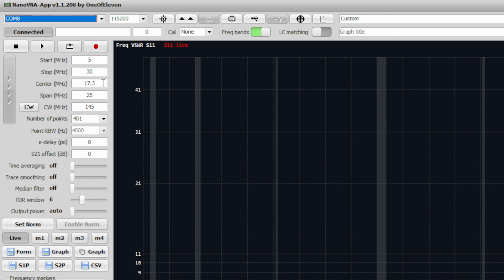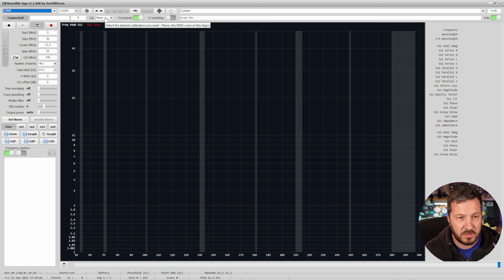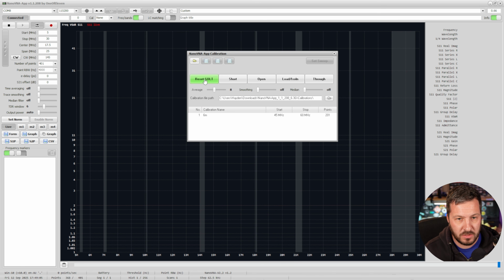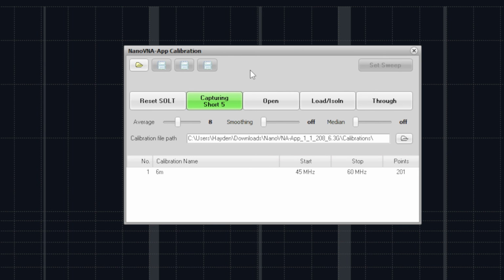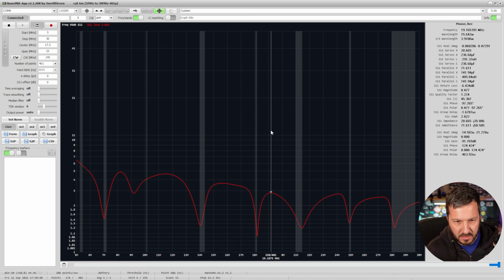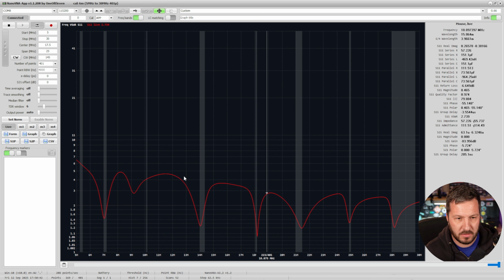So I've changed the frequency to 5 to 30 megahertz. I've also increased the number of points up to 401. What we'll do is stick it into continuous scan mode, and we can go to calibration and reset. Go and do our calibrations as normal. And because we're doing 401 points, you can see here that the calibration is a lot slower. And look at that, we've got quite a few dips going on here now.